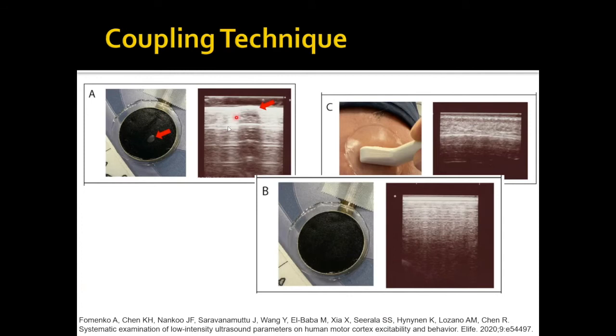In panel A, we have one of those gel patties that we cut and place on top of our transducer. Almost always there's going to be one or several air bubbles from the layering of the ultrasound gel. When we take an imaging transducer and place it on top of that gel patty, we can directly visualize the coupling medium to transducer interface, and you see a large artifact from the bubble. This is bad, so we manually extrude that bubble carefully.